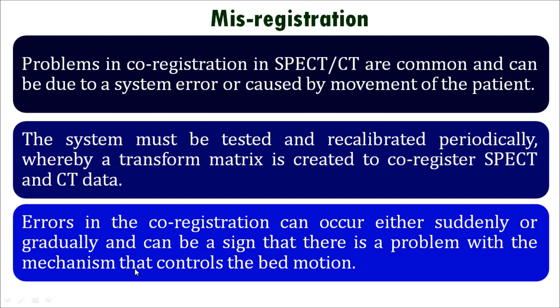Right? If there is any movement, then what will happen? Your SPECT data will not be perfectly registered with your CT data. Second, the system must be tested and recalibrated periodically, whereby a transform matrix is created to co-register SPECT and CT data. Then errors in the co-registration can occur either suddenly or gradually and can be a sign that there is a problem with the mechanism that controls the bed motion.